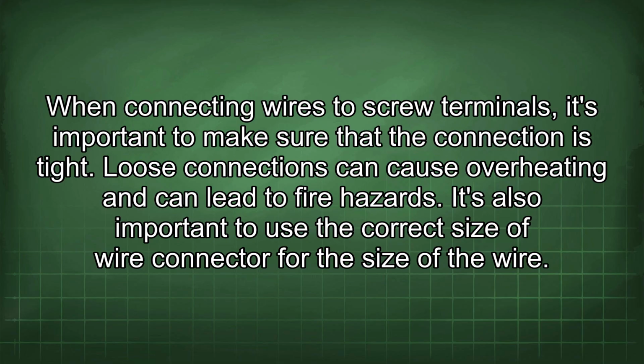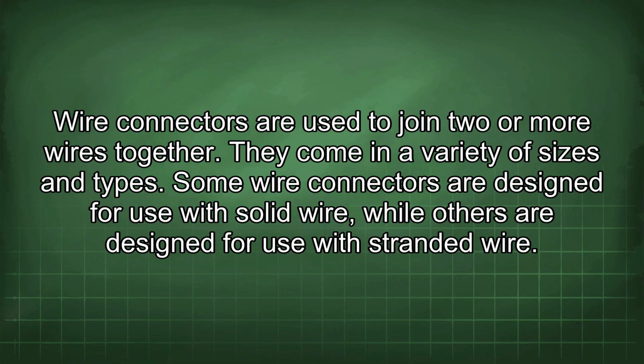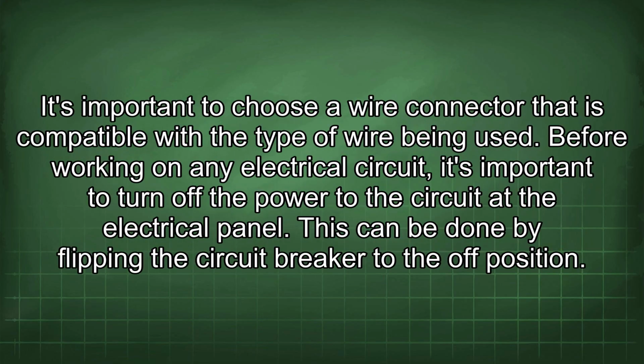When connecting wires to screw terminals, it's important to make sure that the connection is tight. Loose connections can cause overheating and can lead to fire hazards. It's also important to use the correct size of wire connector for the size of the wire. Wire connectors are used to join two or more wires together. They come in a variety of sizes and types. Some wire connectors are designed for use with solid wire, while others are designed for use with stranded wire. It's important to choose a wire connector that is compatible with the type of wire being used.